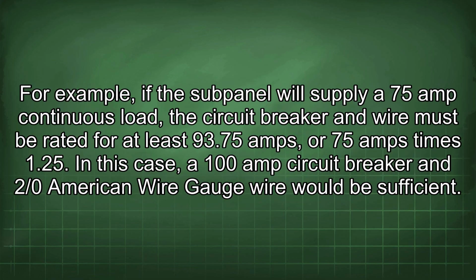For example, if the subpanel will supply a 75 amp continuous load, the circuit breaker and wire must be rated for at least 93.75 amps, or 75 amps times 1.25. In this case, a 100 amp circuit breaker and 2/0 American wire gauge wire would be sufficient.